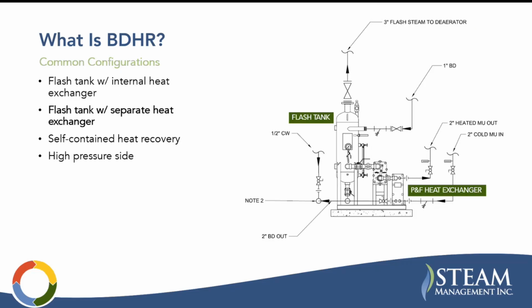Next is kind of the same idea, but with a separate heat exchanger. So if you put this in your PFD, or in your heat and mass balance, it's going to look kind of the same. You have your blowdown coming in, flash steam coming out. You have the drain going to a separate heat exchanger, heating makeup water. I'm really kind of showing makeup water in all of my examples here, but there are other opportunities for heat recovery as well, which we'll talk about in a minute. But the most common is makeup water. The advantage here is that it allows the flash tank and the heat exchanger to be designed and maintained as separate components, so it can offer flexibility in the equipment design and selection, as well as maintenance. It could be easier to access.